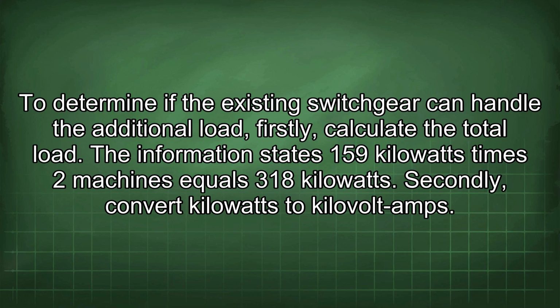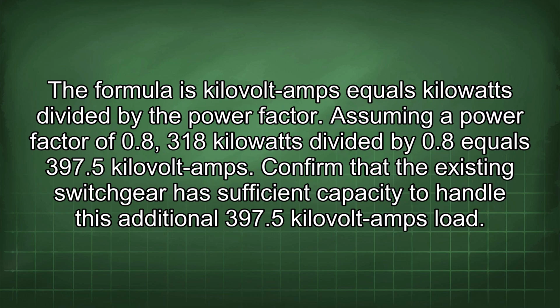Secondly, convert kilowatts to kilovolt amps. The formula is kilovolt amps equals kilowatts divided by the power factor. Assuming a power factor of 0.8, 318 kilowatts divided by 0.8 equals 397.5 kilovolt amps.